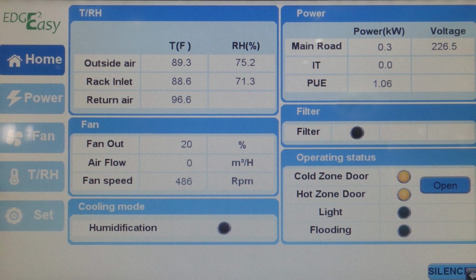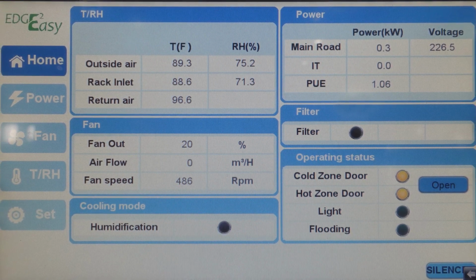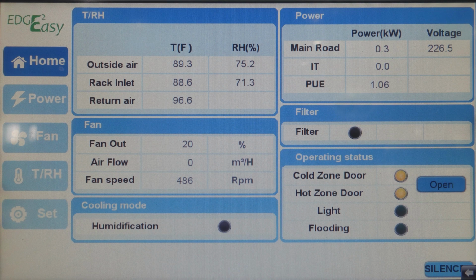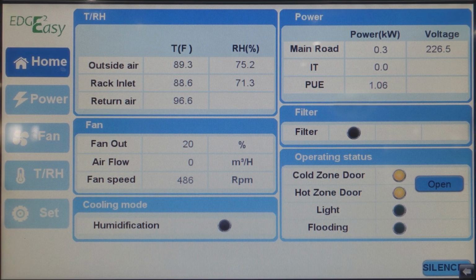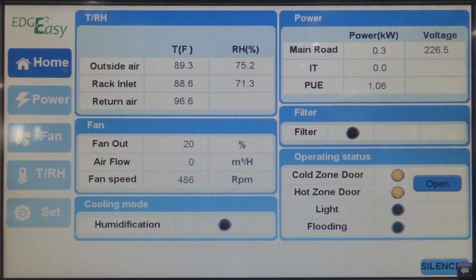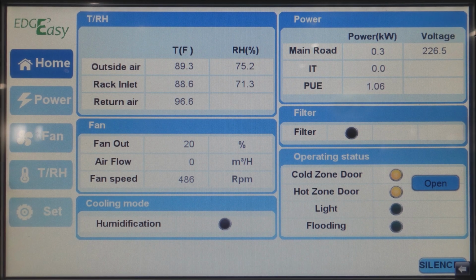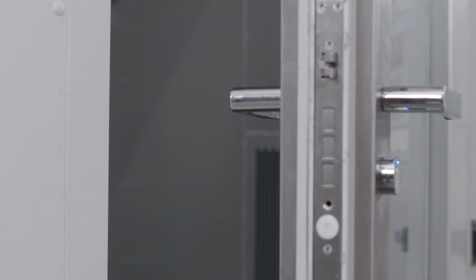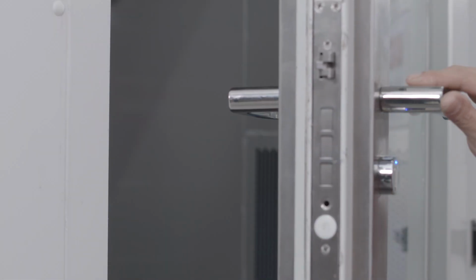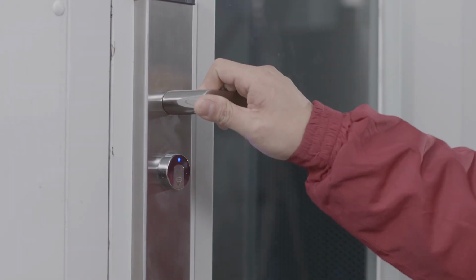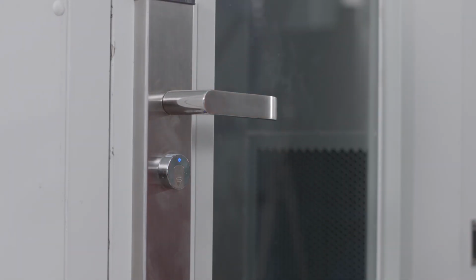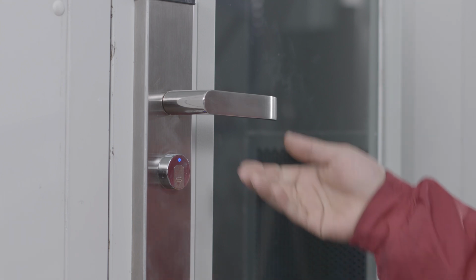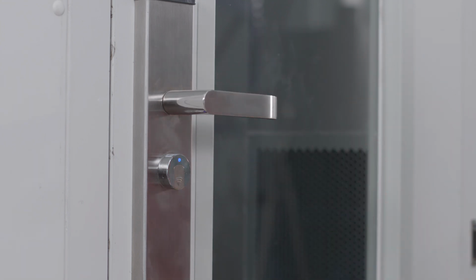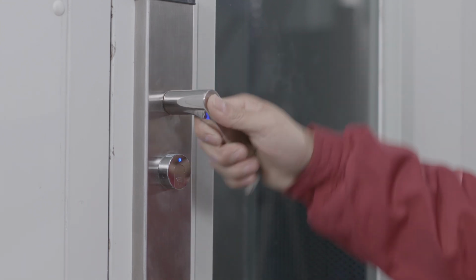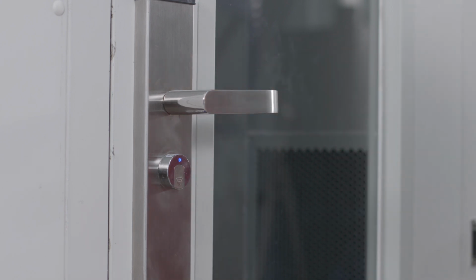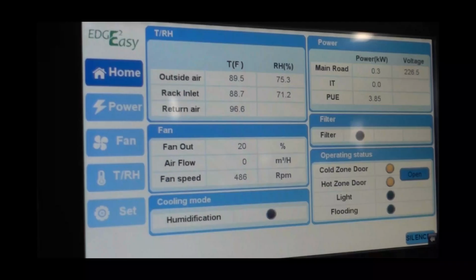From here, you can see what's going on and even do something about it. You can monitor the temperature and relative humidity, fan speed, power consumption, the condition of the filters, as well as control the doors and lights. Security is vital, especially in remote locations. The door locks are reinforced and have several key entry options, including biometrics. They can also be opened from the PLC on-site or remotely.